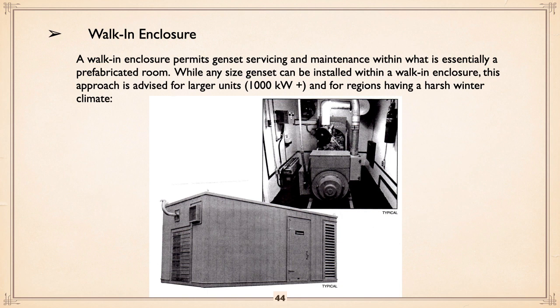Walk-in enclosures. Let's take it a step further. The enclosure can be large enough that you can actually walk into it. Essentially, it's a prefabricated genset room. And any genset can be installed within a walk-in enclosure. This approach is advised certainly for anything at or over 1,000 kilowatt, and in harsh winter climates. You can have it nice and toasty and warm inside, and away you go.